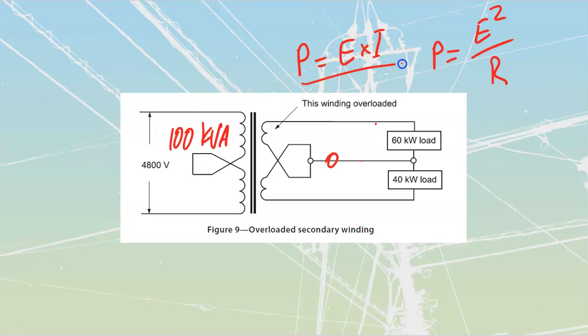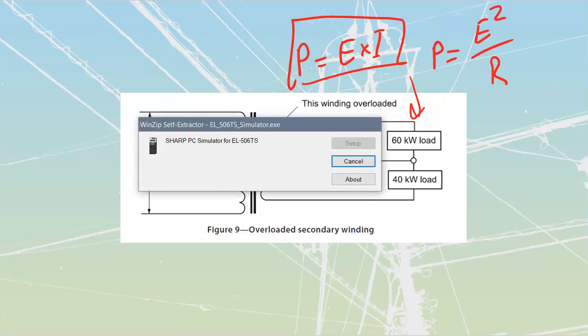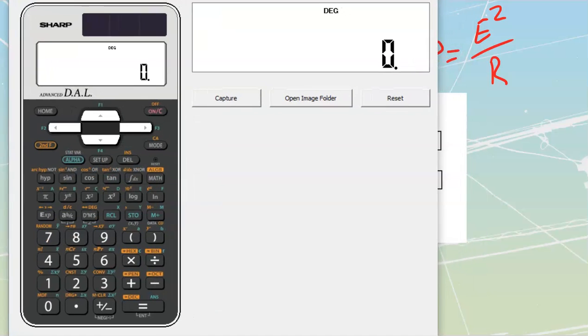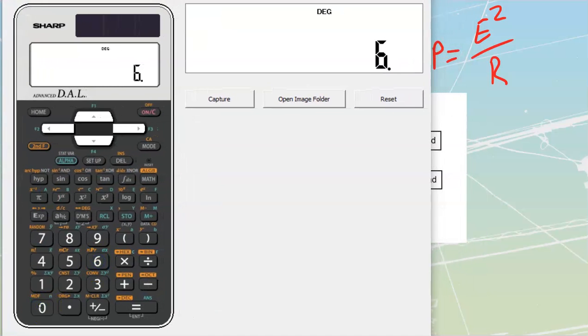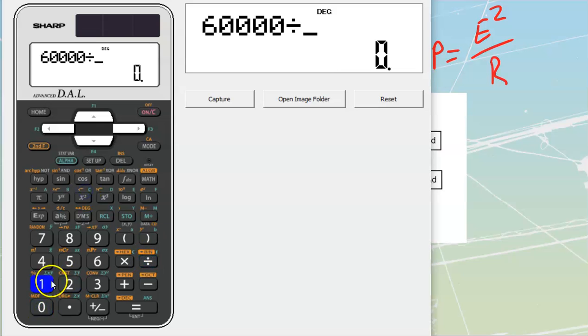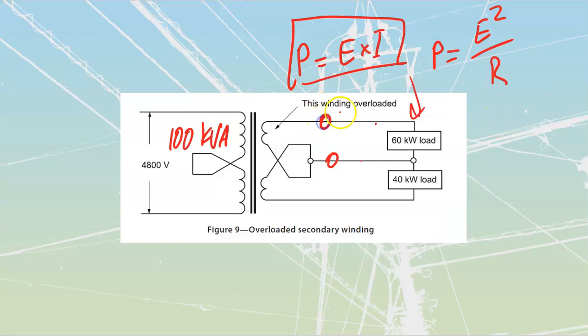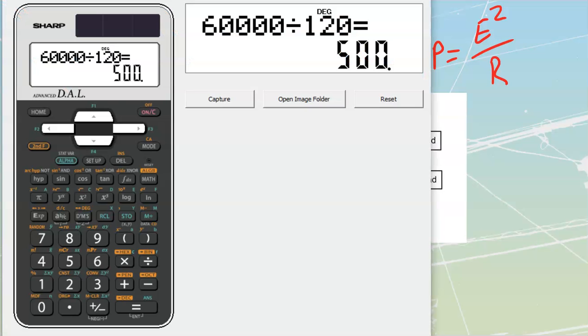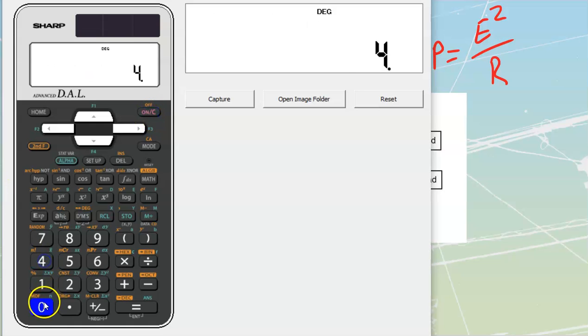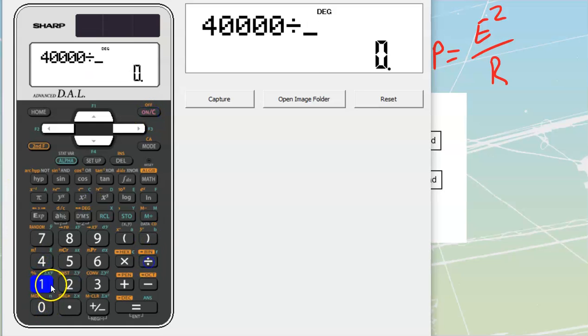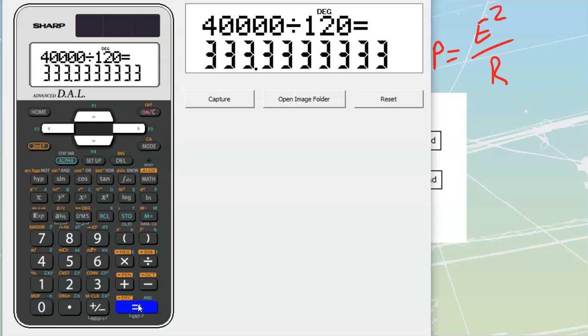Let's work with power equals E times I for a second, and we're going to figure out what current we have inside of here. Pull up that calculator. We have 60 kilowatts, so 60,000, divided by 120, because that's what we have going across this section right over here. And when I do that, I come out to a total current of 500 amps that I'm going to be pulling through this leg. 500 amps is going to be going through there. If I go to the other winding, 40,000 divided by 120, I'm coming out to 333 amps over here.